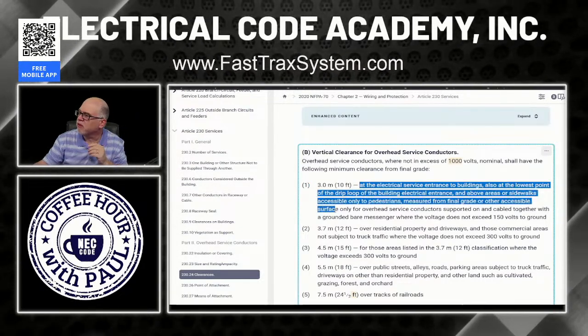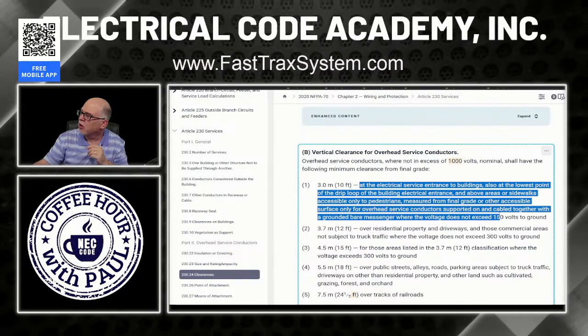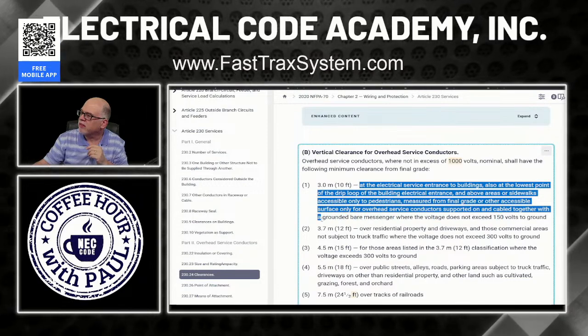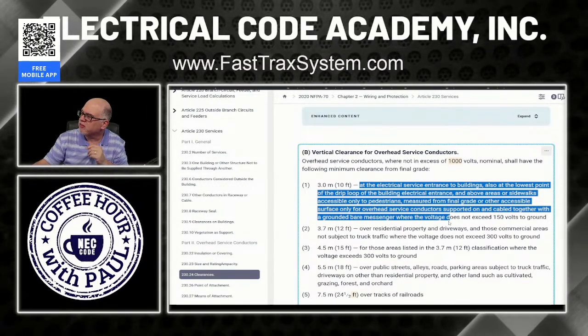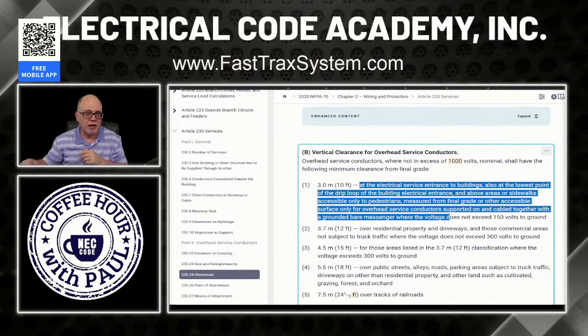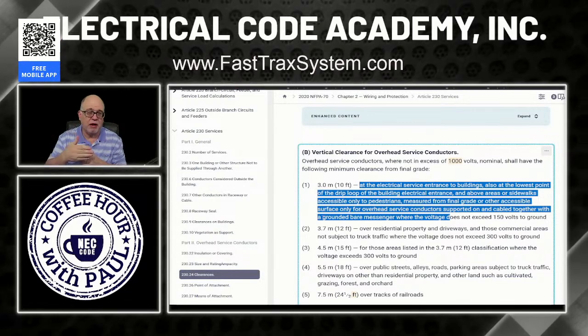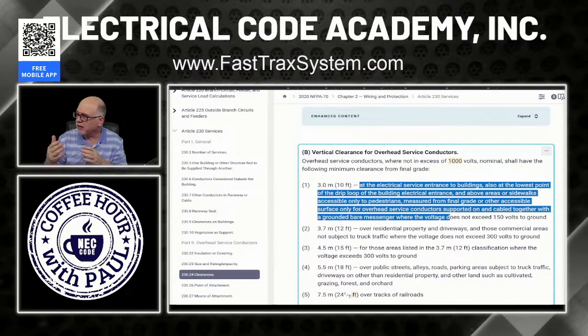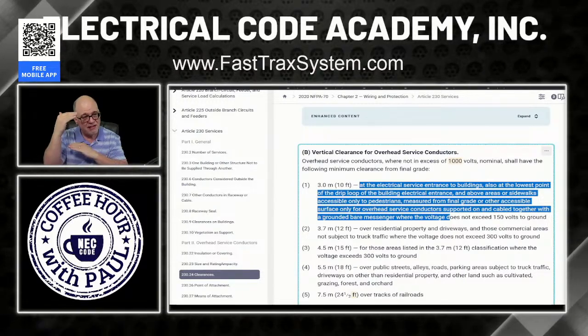And it says surface only for overhead service conductors supported on or cabled together with a grounded bare messenger where the voltage does not exceed 150 volts to ground. Okay, so that's a 120/240 drop. Any one of the phases to ground is going to be 120. So again, it does not exceed 150 to ground. Okay, so we have to have that 10-foot clearance.